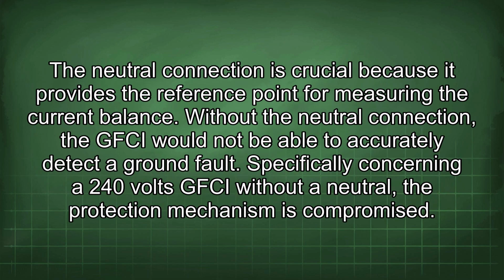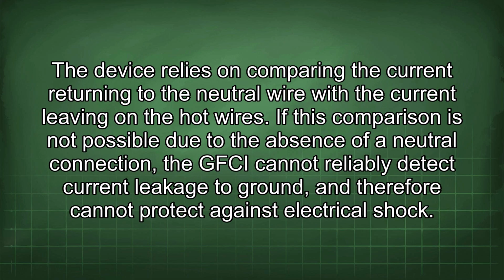The neutral connection is crucial because it provides the reference point for measuring the current balance. Without the neutral connection, the GFCI would not be able to accurately detect a ground fault. Specifically concerning a 240 volts GFCI without a neutral, the protection mechanism is compromised. The device relies on comparing the current returning to the neutral wire with the current leaving on the hot wires. If this comparison is not possible due to the absence of a neutral connection, the GFCI cannot reliably detect current leakage to ground, and therefore cannot protect against electrical shock.